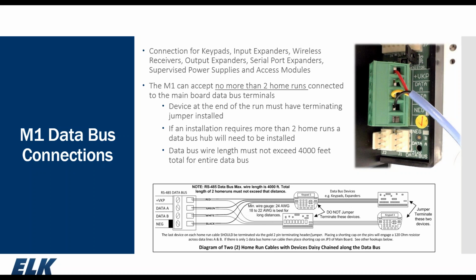Now, if we were to power down the system and measure the resistance across A and B here at the panel, we would read between 60 and 70 ohms. It puts the two resistors in parallel. It's a troubleshooting tip that tech support may ask you to do if you call and say, I'm having a data bus issue.